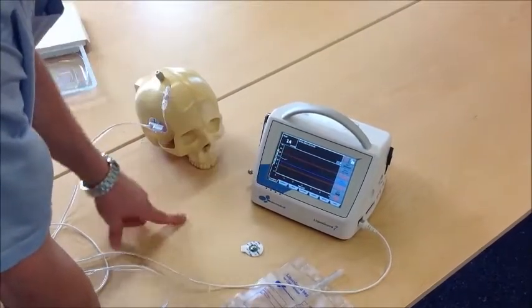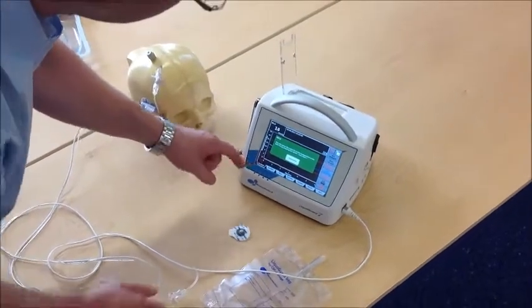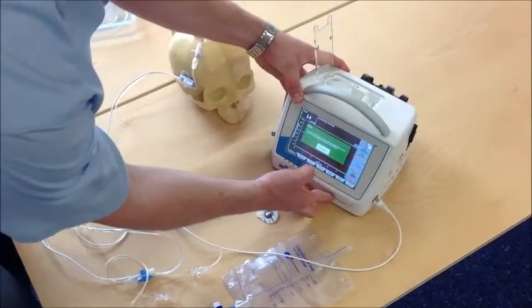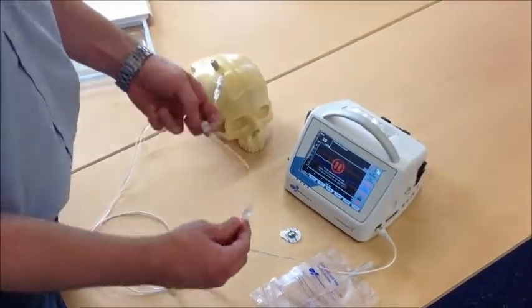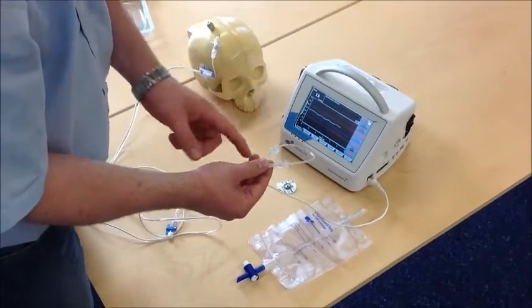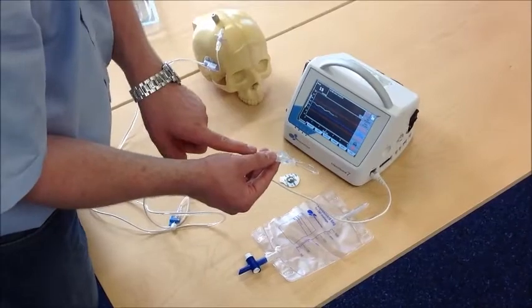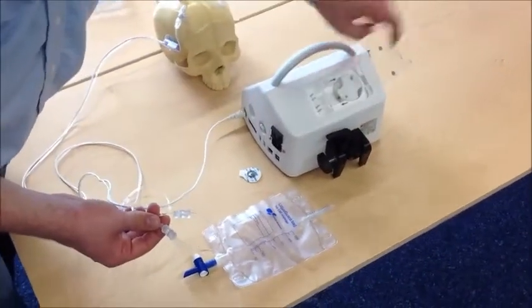As long as the machine is in pause mode, you can open the cover clasp, providing a window with a button. When you turn this button, the rotor starts to turn. To insert the tube into the rotor, the two connectors have the shape of an arrow, in this situation leading in that direction.